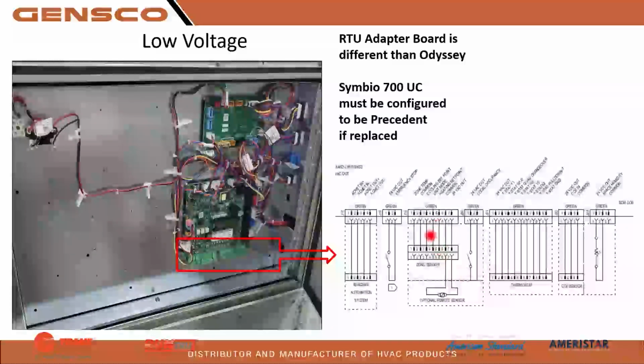Here's our zone sensors. If you're using zone sensors, CO2 detector, we get a lot of calls. This does wire into the J22 on the Symbio control board. So if you have a CO detection system, it's right there. And remember, a Symbio 700 UC must be configured to be precedent if replaced. So if we do have a short circuit or some reason this Symbio control board has failed, you put a new one in from factory. It's all programmed and set up with whatever factory ordered accessories you have. You replace this board, you have to go through and set it up with exactly what you have in the system. So keep that in mind.